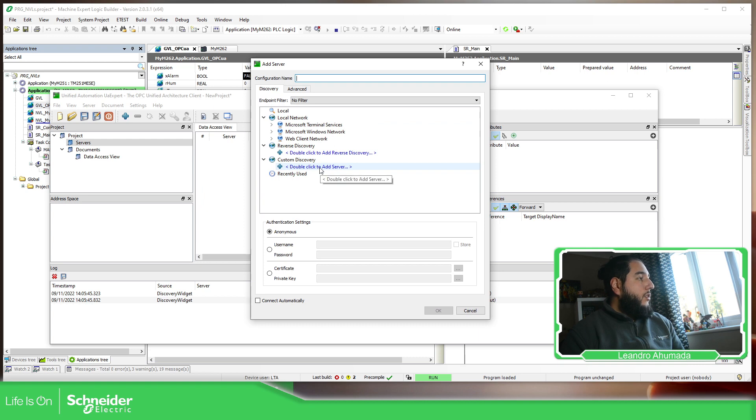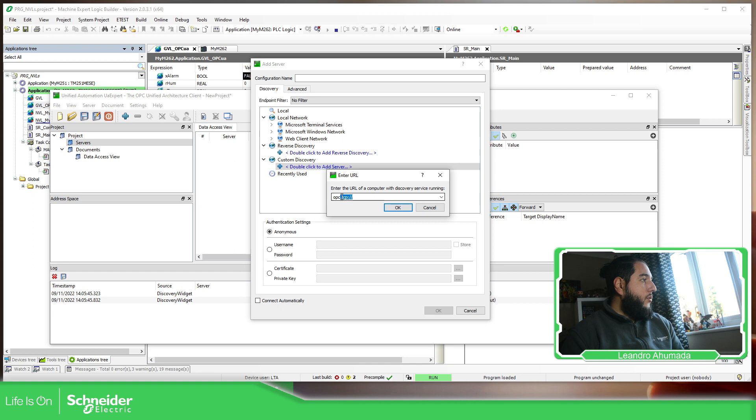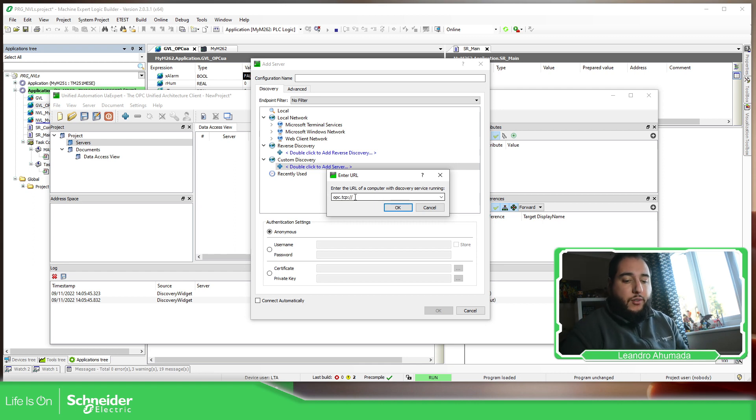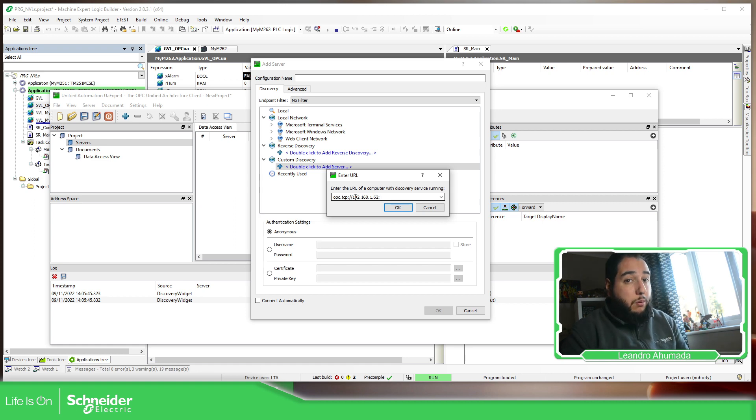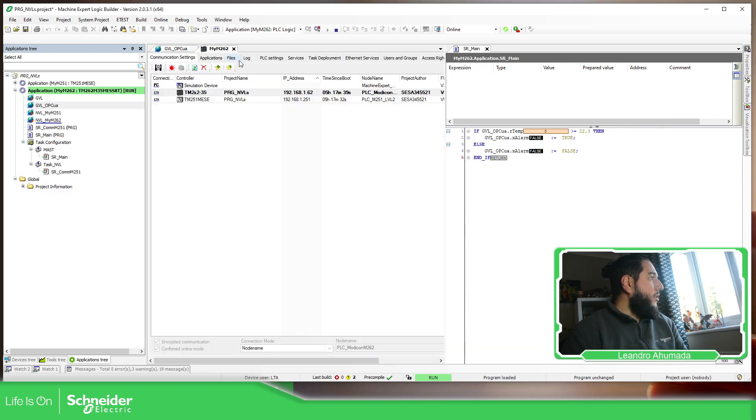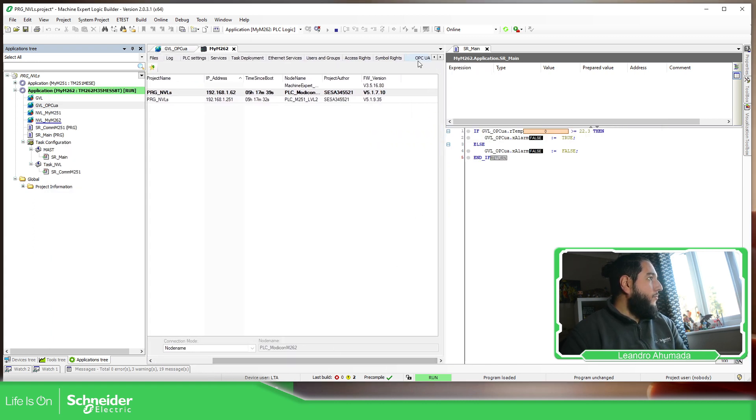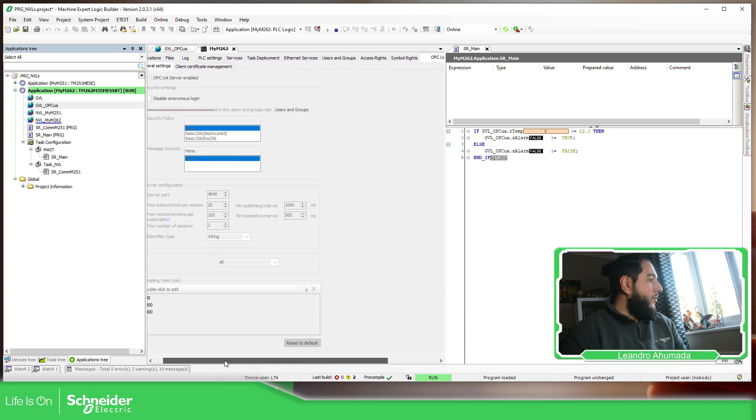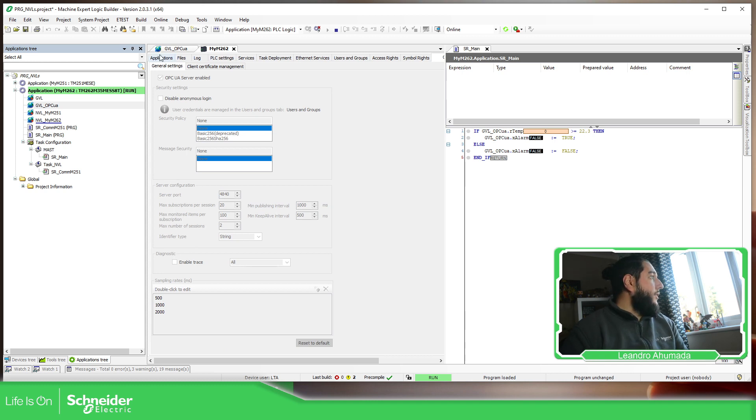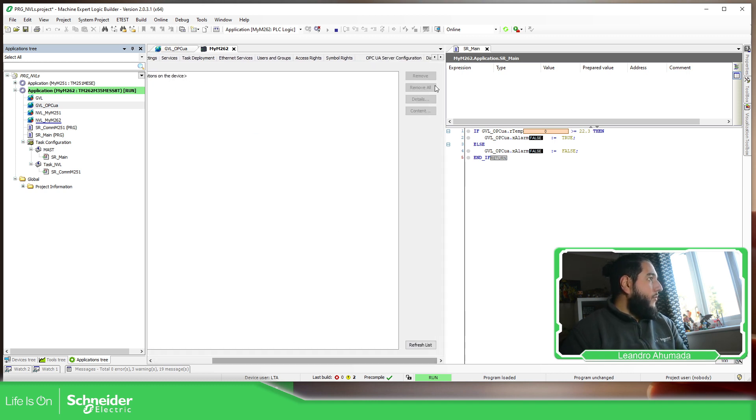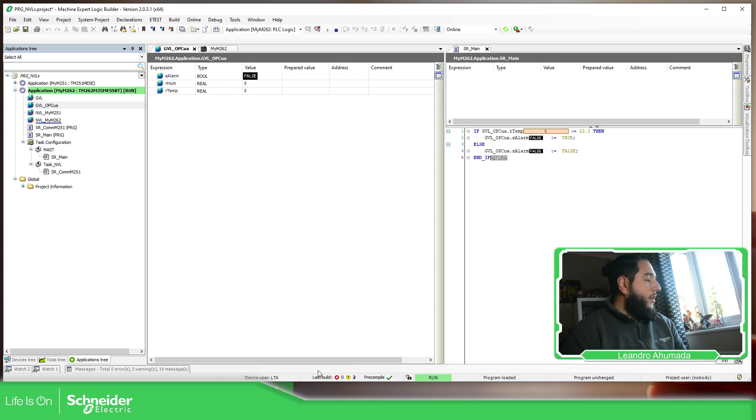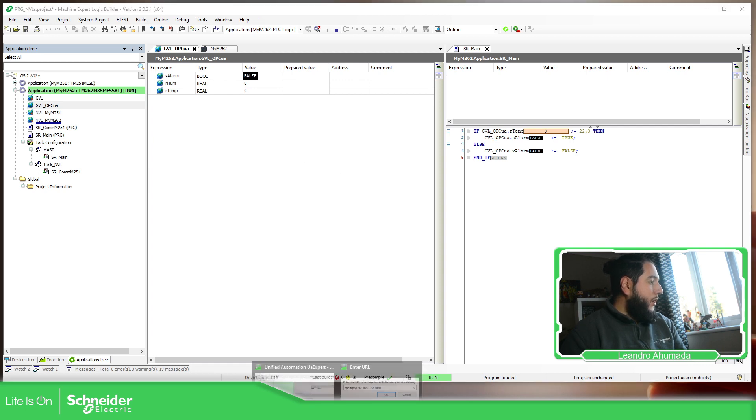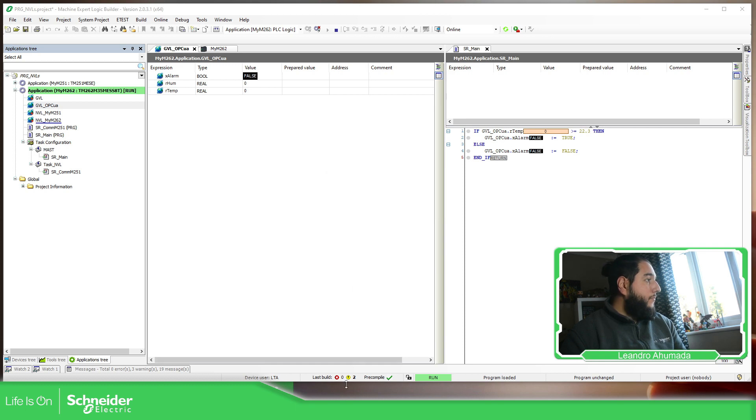Then over here, we just need to add our server. If we double-click, we use this starting address, opc.tcp. And here we just need to use the IP address of our equipment, 192.168.1.62, which is the one I have. And then we just need to use the port of the OPC. As you can see, in our case, it was 4840. As you can see over here, 4840. So let me just back to this view and select here. Okay, good.